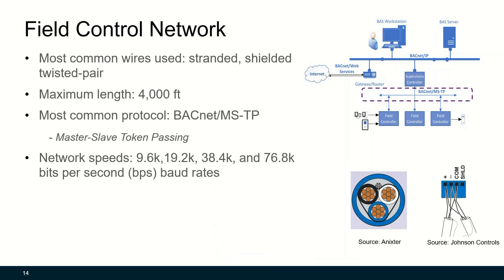The field control network is used to communicate among field controllers. The most common wires used are stranded, shielded, twisted pair. The maximum length is about 4,000 feet. The most commonly used protocol is BACnet MSTP (Master-Slave Token Passing). The network speed ranges from 9.6 kilobits per second to 76.8 kilobits per second.